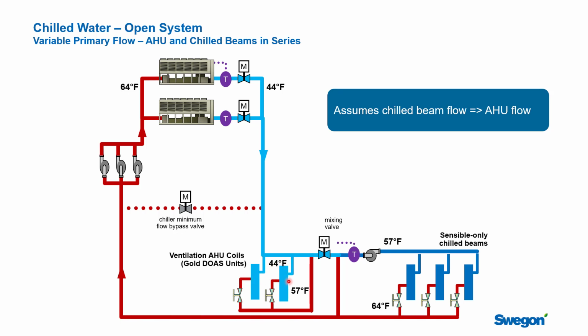we run more ventilation air through these things than you would in, say, a VRF or a 4-pipe fan coil system, because we need enough air to make the beams work properly and to be able to do the dehumidification. So if you step back and add up your loads to your air handling units and you look at the tonnage that you need for the beams, they're going to be pretty close to being on par. They're certainly not going to be 4 to 1 apart. This is going to be roughly 50% and this is going to be roughly 50%. It completely depends on your location and the building application, but they're much closer to being on par.